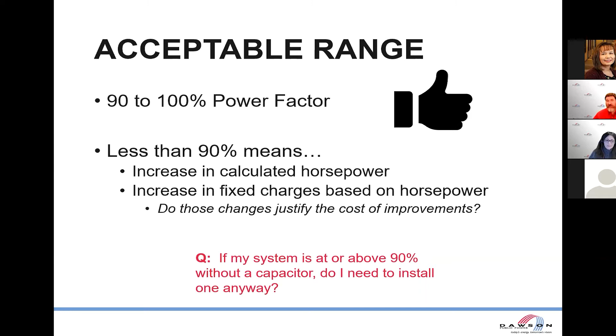So if your system is above 90% without a capacitor, do you need to install one anyway? The answer is no. If you're above 90%, you're good enough. Whether that's because you have a VFD, an incredibly efficient motor, or for whatever reason, if you're above 90%, don't worry about it. You're not going to get an additional charge. So no longer will we be out looking for that capacitor, right? If you're above 90%, we don't care how you got there, just that you're there.